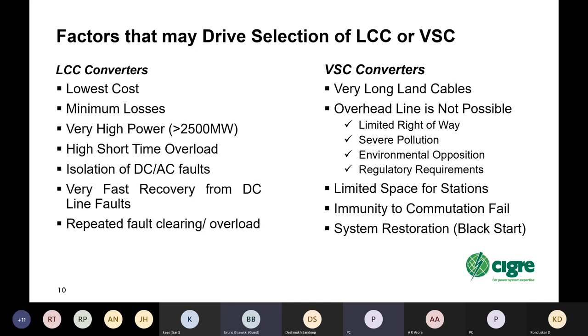Looking at VSC converters, if you have very long land cables, it's possible to use cheaper extruded cables, which may not have capability for voltage reversals, with VSC, because VSC converters inherently don't allow voltage reversals because of the freewheeling diode. So the cables can be cheaper. That is changing now as cable technology is improving. But still, I think, an applicable consideration.